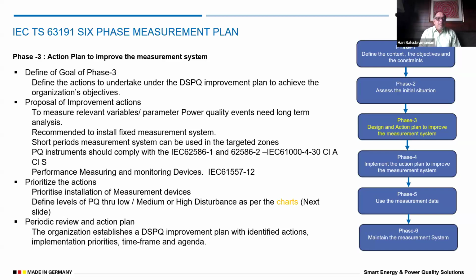So what is the proposal for improvement action? Probably we can target specific zones. This zone I wanted to fix with certain kinds of PQI meters, because these application loads require more, since I have more variable frequency drives in this particular application or use. I will have a better meter in these places rather than a PMD product, I will have PQI. So we have to choose accordingly at various zones and applications, and try to improve the monitoring system from level A to level B, or level 0 to level 1.